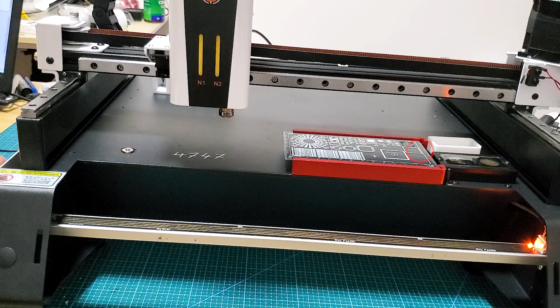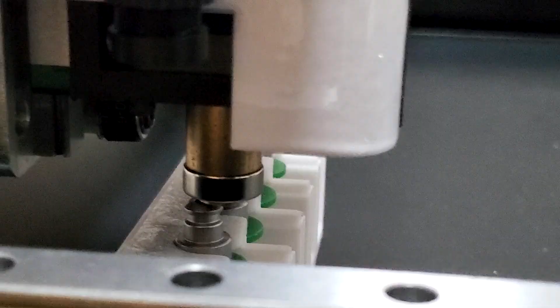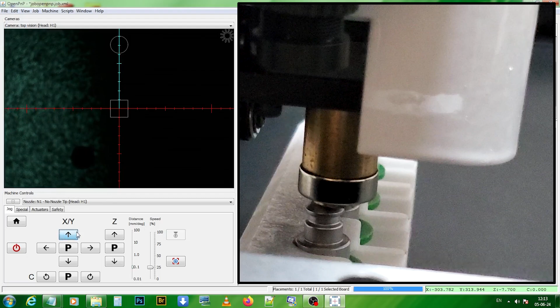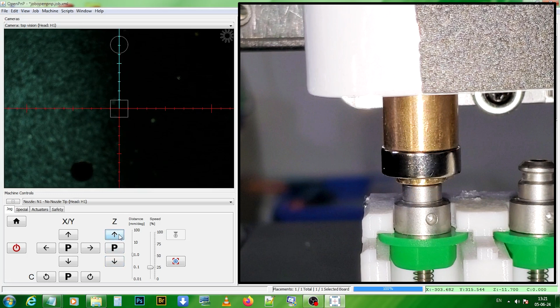We check the positions. As we see, we need to correct the position. We set 0.1 mm in the jog control, and we move the head to correct the Y alignment. We do the same if we need to correct the X alignment. Now we try to go down by 1 mm. It seems the head needs to be moved to the right a little. We fix the X alignment by 0.1 millimeters.